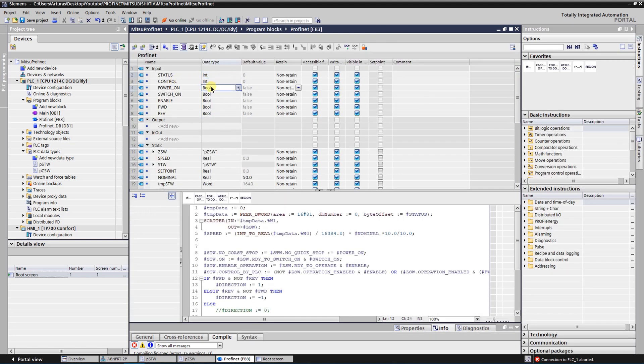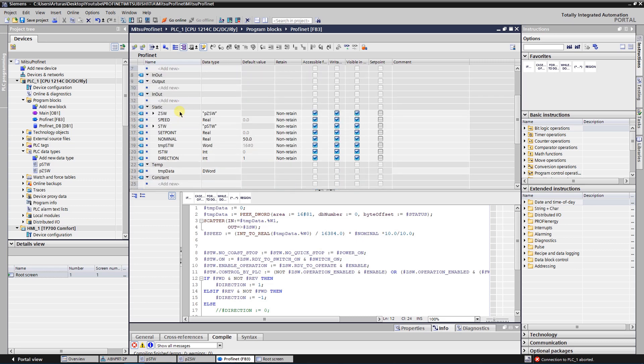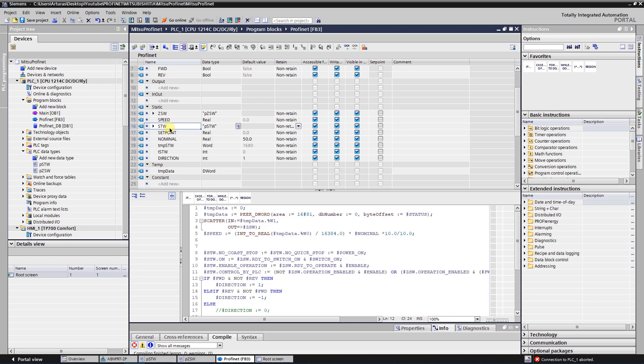Then we need to set those bits power on, switch on, enable, and forwards and reverse directions. In the STATIC section, I have added ZSW which will be STATUS BITS and STATUS SPEED. STW will be CONTROL BITS, and SETPOINT is the setpoint speed. And NOMINAL is the value for setpoint, because here is going to be used NSOLLA 16-bit setpoint, which is percent over the nominal speed of the motor.